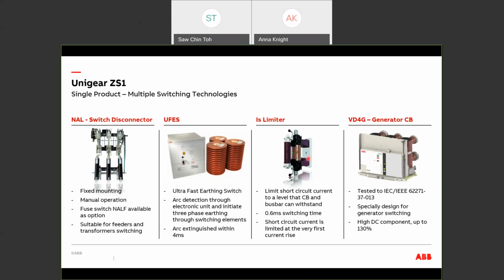Next is the IS limiter. The IS limiter is deployed to limit the short circuit current of the switchboard. Upon detection of the short circuit current, this unit will activate within 0.6 millisecond and limit the fault. This unit is normally installed between the bus sections.